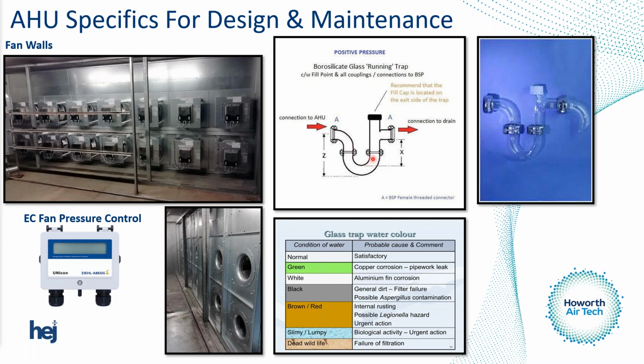The water that sits in the trap is also an indicator of how the AHU is performing. Black water or general dirt coming through could indicate filter failure. In an old air handling unit with belts inside, it could be a sign the belts are starting to corrode or need replacing, along with other issues that can lead to nasty microbiological problems needing to be addressed.